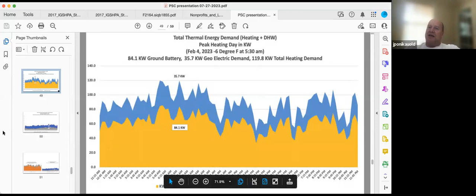If that is reduced during the day, because now the sun comes up, the battery contribution has been reduced automatically—it follows the total energy use. So the total heating and hot water usage automatically adjusts. That's fascinating—this is not the delta T, this is actually directly kilowatts. If you're looking at the delta T, this is what you see in the wintertime, and it goes up and down depending on how many heat pumps are turning on and off in that moment.